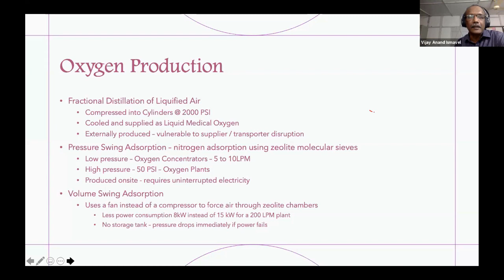The same process is also used for oxygen concentrators. There is another technology called volume swing adsorption, where instead of a compressor, air is forced through the chambers using a fan. This consumes much less power, but the problem is that if power stops, the pressure immediately drops to zero, so there is a risk of taking out too much oxygen from the standby cylinders.